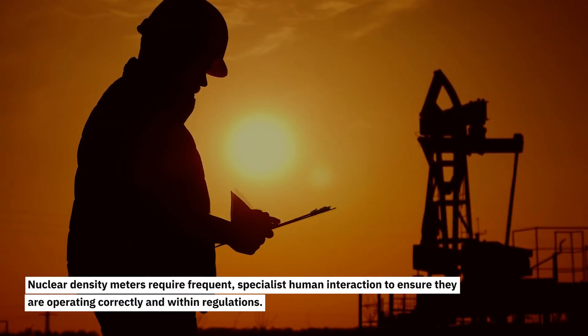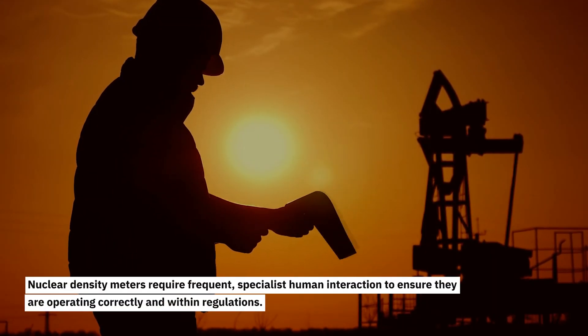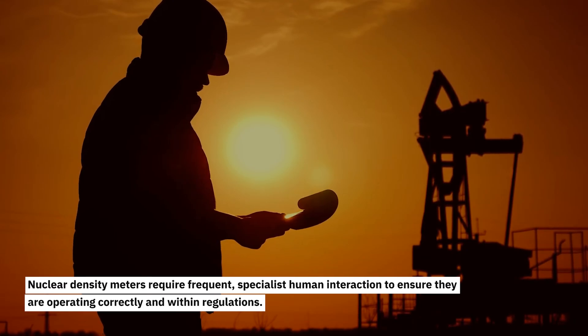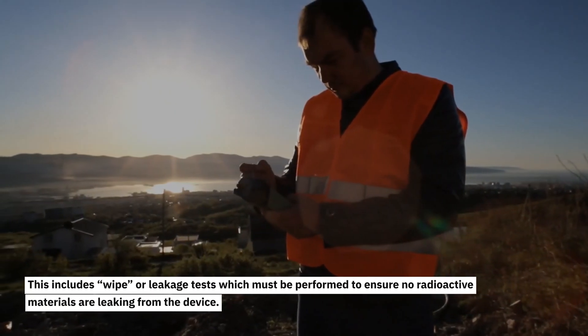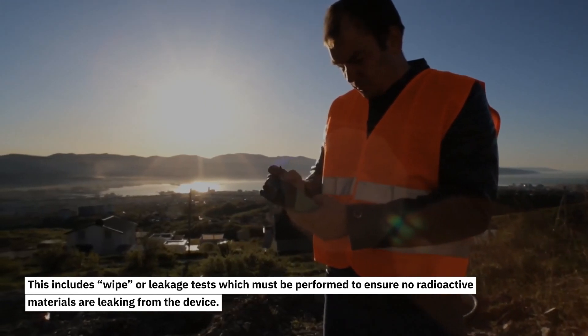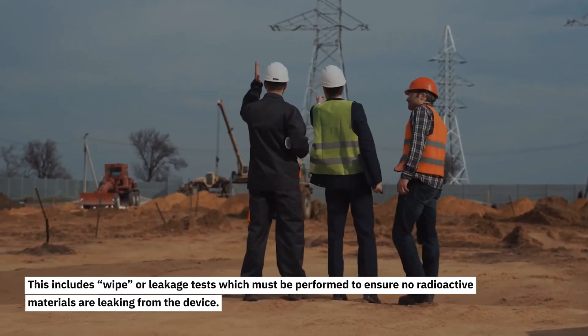Nuclear density meters require frequent specialist human interaction to ensure they are operating correctly and within regulations. This includes wipe or leakage tests, which must be performed to ensure no radioactive material is leaking from the device.